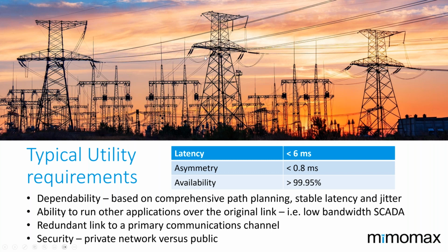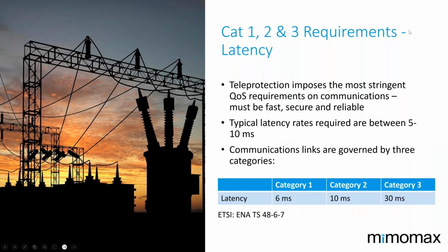When we look at the categories of requirements, these categories can be found in some of the ETSI standards, particularly in Europe. ENA TS 4867 is one of them, and it depicts the types of latency required for various categories of teleprotection, with 6 milliseconds being the most stringent and 30 milliseconds being the most relaxed. This imposes the most stringent requirement on QoS to maintain fast, secure, and reliable comms. Typical latency rates we're seeing are between 5 and 10 milliseconds, but a lot of our customers are shooting for category 1 requirements using Mimomax equipment to achieve that.